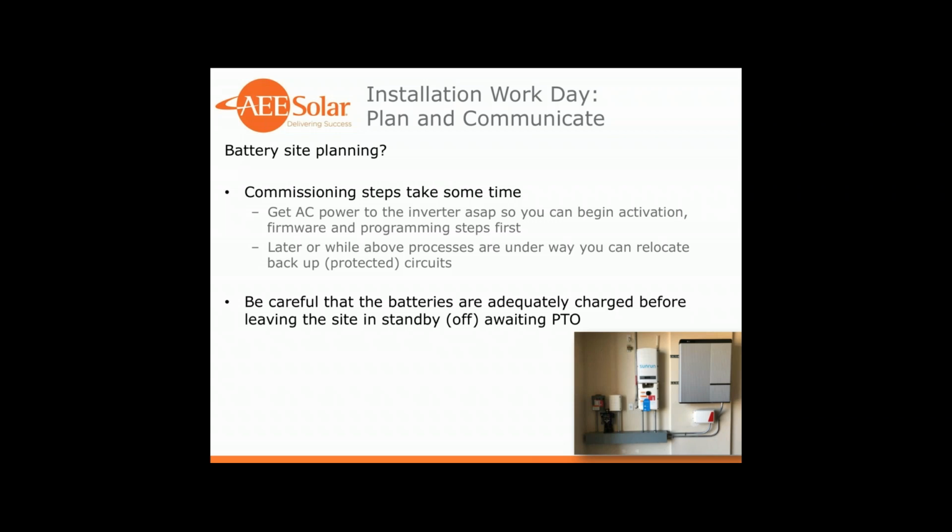Again, if anybody here is doing battery systems, I'd be really curious if you have any insights or techniques. We typically want our batteries charged to at least 50% before we turn them off for standby for a couple of weeks, awaiting the local inspector and utility inspection as well. That's our way of ensuring that we don't have equipment that needs to be reviewed or repaired.